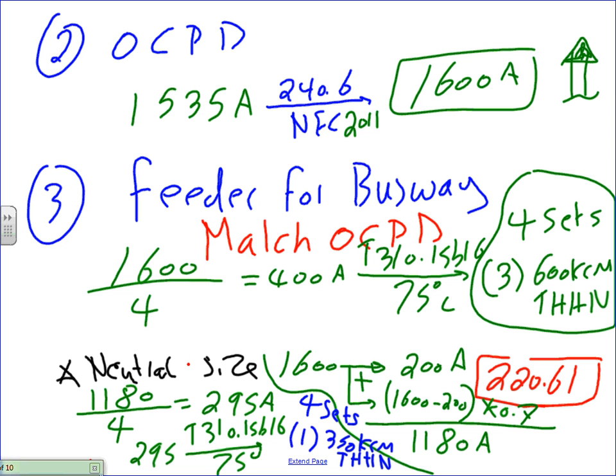Did you add them up? Did you add the 200 to it? Yeah. I don't do all the steps, guys. It makes sense when you add the 200. Cool. So what this would do to you guys, it'll get you a smaller neutral. Now, William, my friend, 95% of the time, your neutral does not exist in a busway. You don't need a neutral. All of them are three phase. So you don't even carry a neutral conductor. It would be a waste of money.